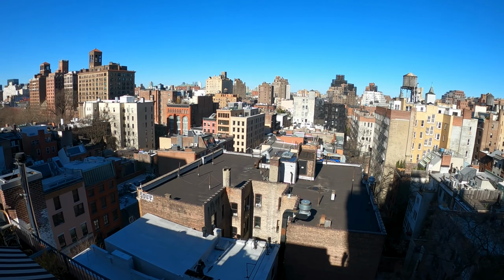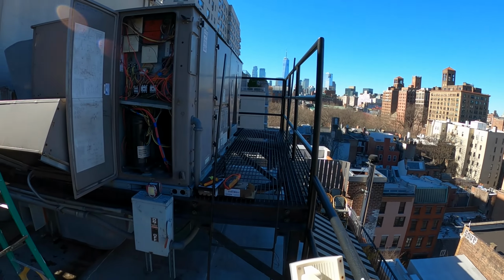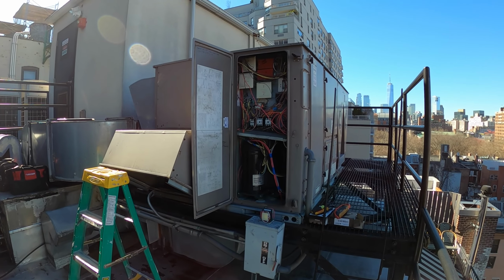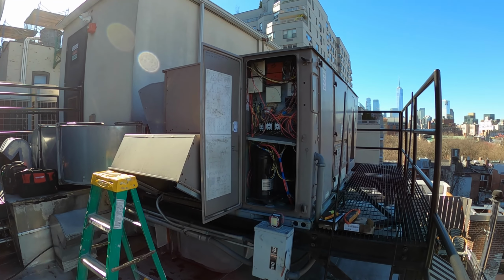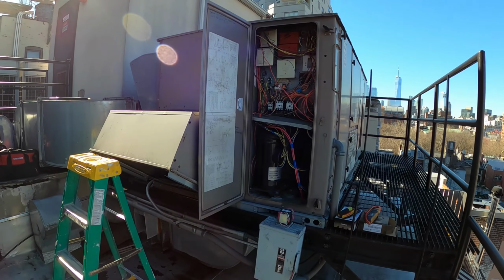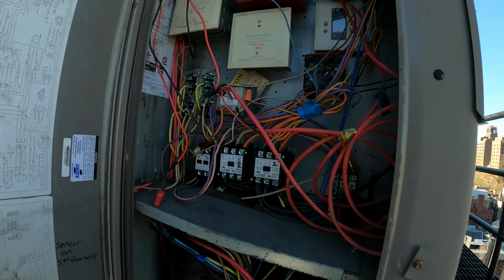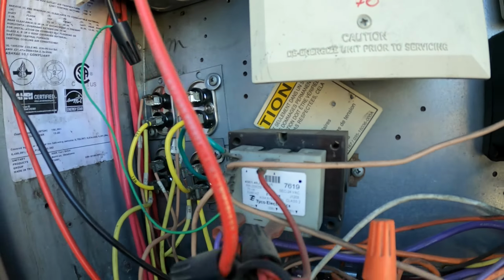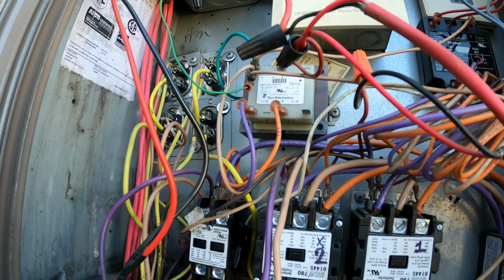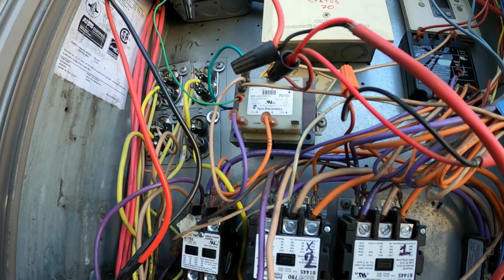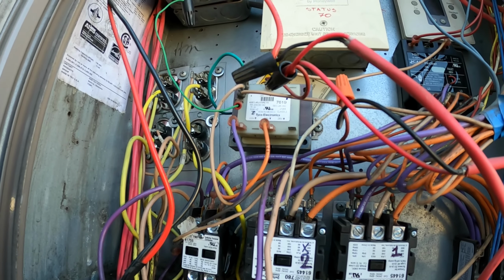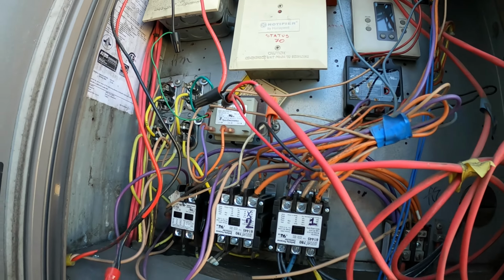Today we're working on a York package rooftop unit. We had a faulty transformer, and we're going to be upgrading it, but we're not just replacing it, actually upgrading it. So here we have the very old transformer. This is a step down transformer from 208 volts down to 24 volts, 75 VA.